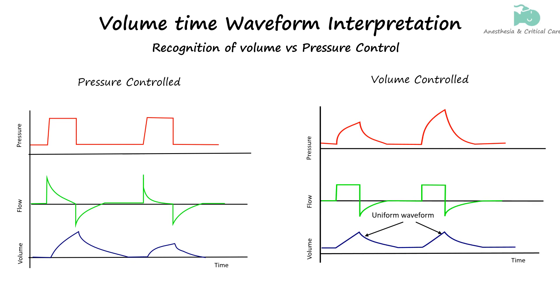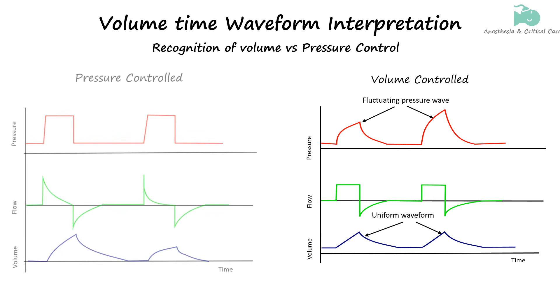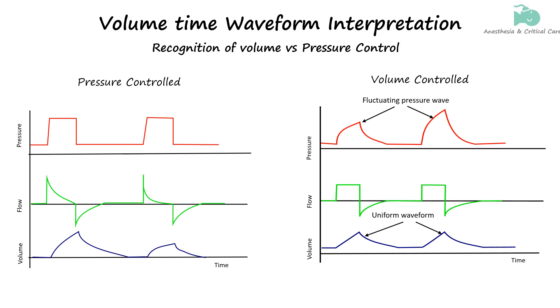This is because in volume-controlled ventilation, the ventilator maintains a constant volume, leading to a uniform waveform. Additionally, while the volume-time waveform remains consistent, the pressure-time waveform may vary depending on the patient's lung compliance and airway resistance. In contrast, in pressure-controlled ventilation, the volume-time waveform may change with varying lung conditions, but the pressure-time waveform remains consistent, indicating that pressure is the controlled variable.